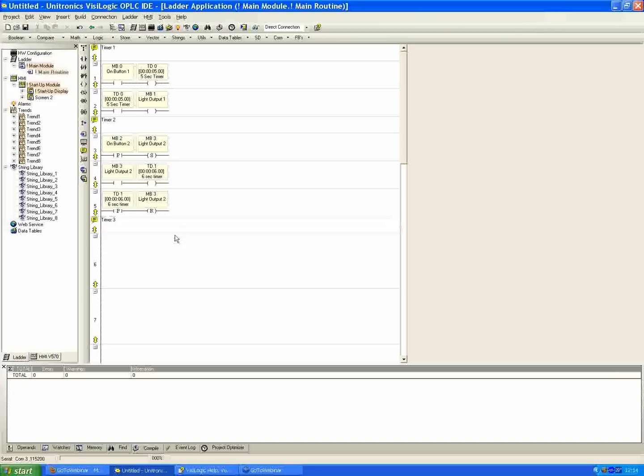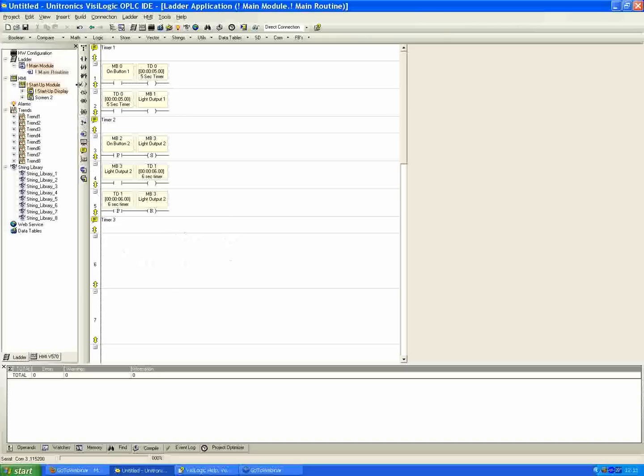The previous two methods for implementing the timer that we have used required either holding down a button or pressing the button a single time. But if for some reason you want a timer to just always be continuously counting down for five seconds and then doing whatever it's assigned to do, whatever condition output you want to utilize, and then have it count down again right away. So we're going to make a timer that's constantly counting down all the time. To do that, we will use this time an inverted contact available under the center pane here, or also the Boolean contacts and inverted contact.